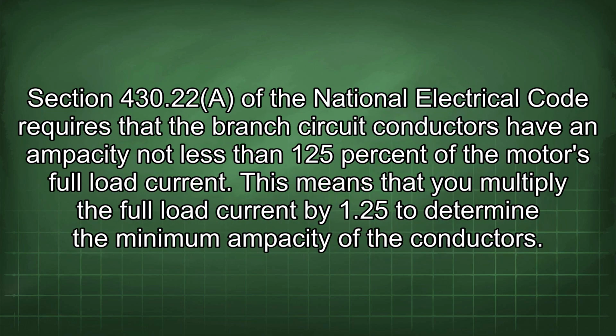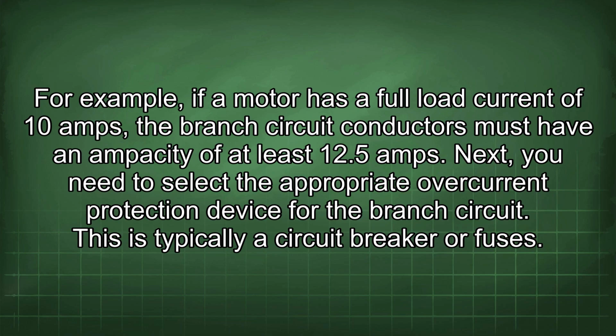Section 430.22 of the National Electrical Code requires that the branch circuit conductors have an ampacity not less than 125% of the motor's full load current. This means that you multiply the full load current by 1.25 to determine the minimum ampacity of the conductors. For example, if a motor has a full load current of 10 amps, the branch circuit conductors must have an ampacity of at least 12.5 amps.